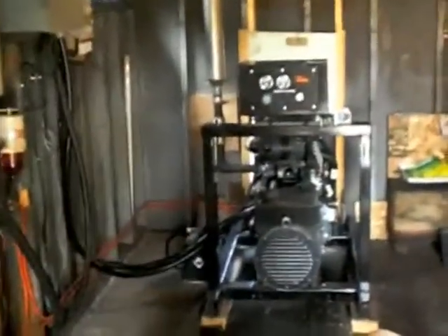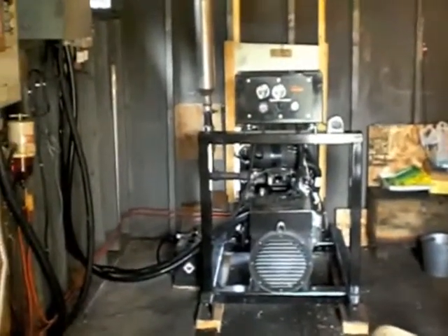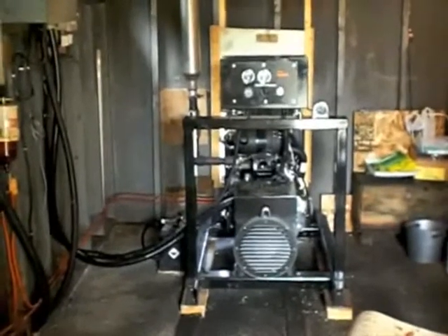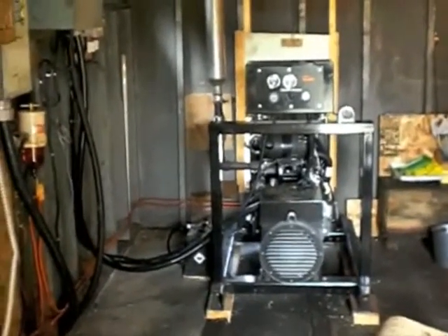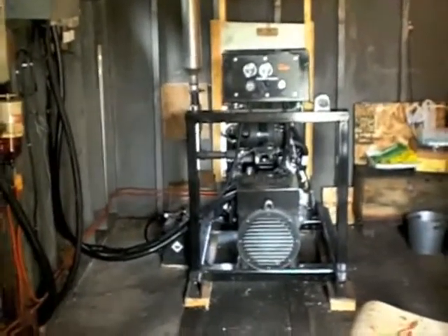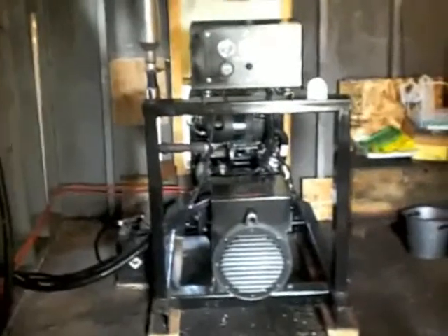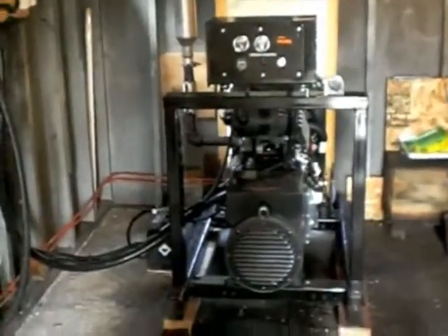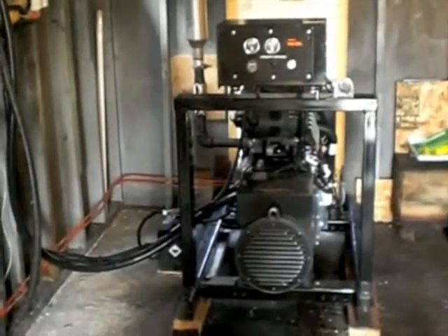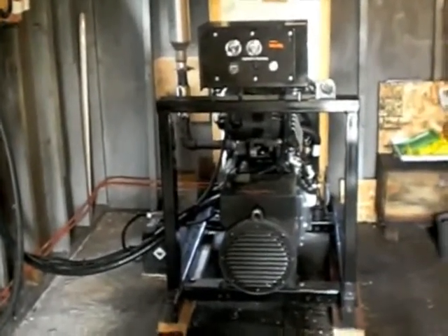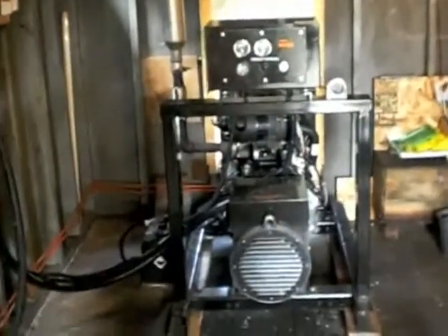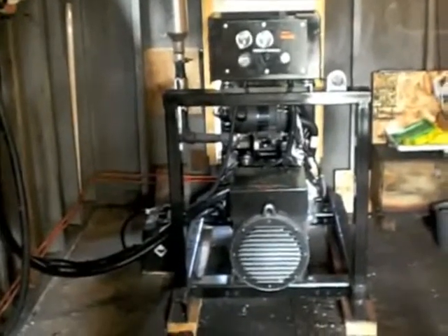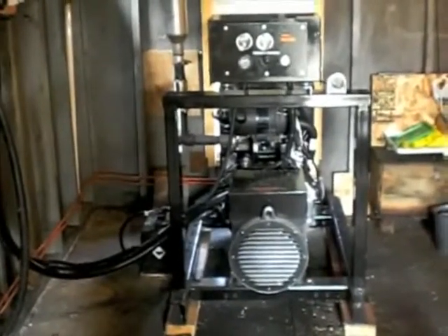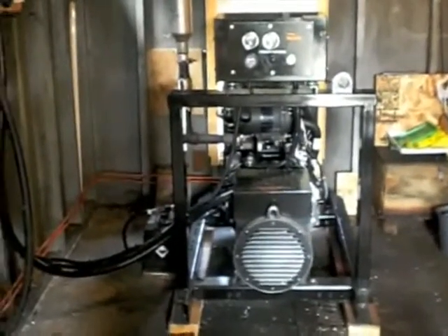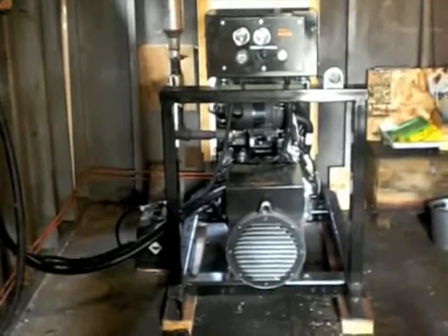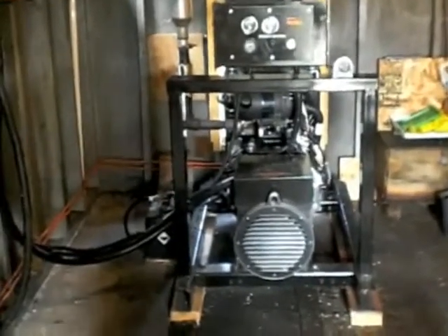And this is their main generator. It's an 18 kilowatt Isuzu diesel generator, and this before now had been running pretty well every day to keep the power needs of the center running. And it's obviously a very costly venture to keep that running, and that's pretty well the reason why we did this project, was to eliminate the usage of the diesel generator and to reduce their fuel consumption overall. So as we mentioned earlier on, this generator has the ability to start and to feed the loads here at the center. Also, it will charge the battery bank that is in the shed up there on the hill.